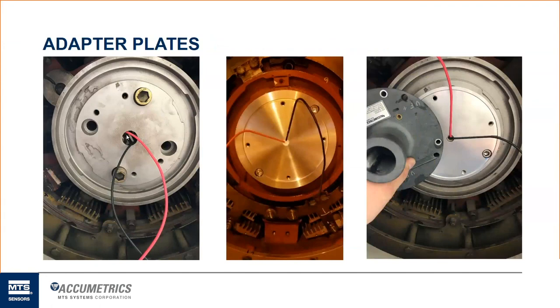We then can run wires down to the bus bars, which are underneath this. So one side would be positive and the other side is the negative side of the field. Then we provide an aluminum adapter plate that picks up the existing holes that are already in the rotor end cap. So again, the customer doesn't need to machine or drill and tap any holes for that. We try to design everything so that it can pick up what's already there and make it as easy as possible for them to retrofit this equipment into their generator.